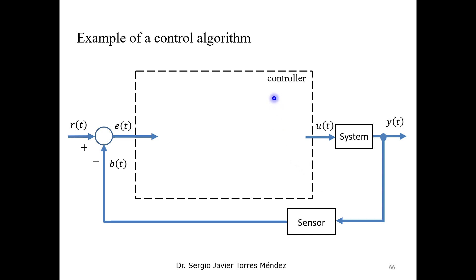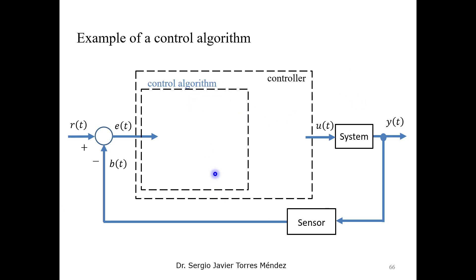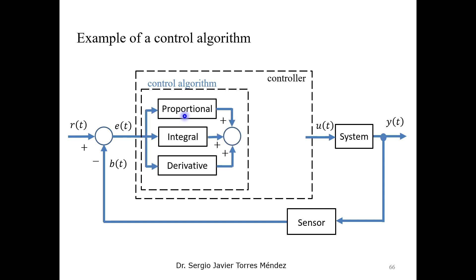Focusing on the controller block, we have additional important elements called control algorithms, which include the formula or control law that generates a signal to a driver affecting the actuator. For example, the proportional-integral-derivative (PID) control law uses the error input to generate a signal to the driver, which in turn generates the final signal to the actuator.